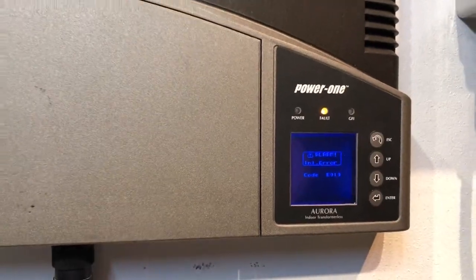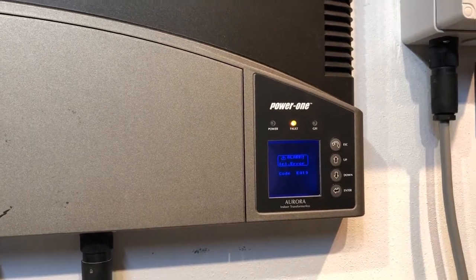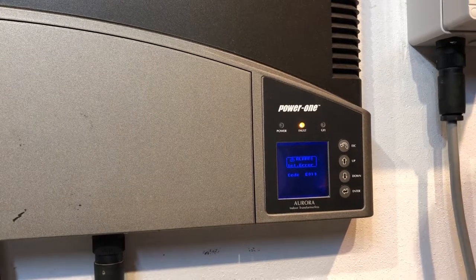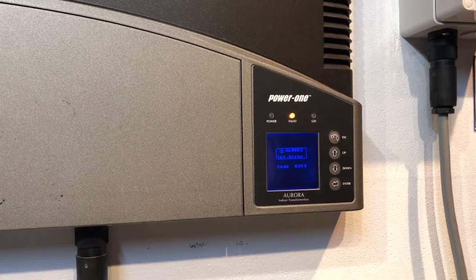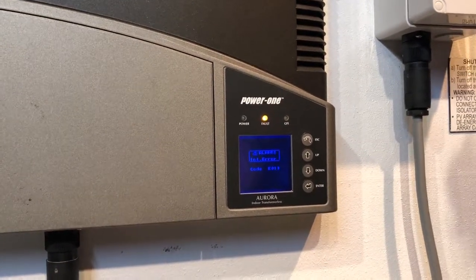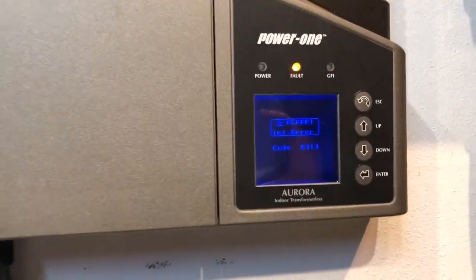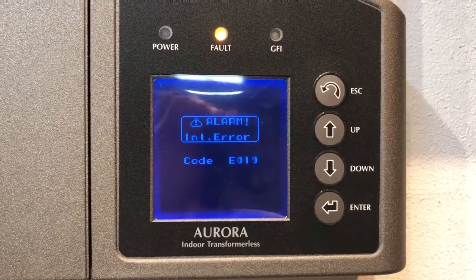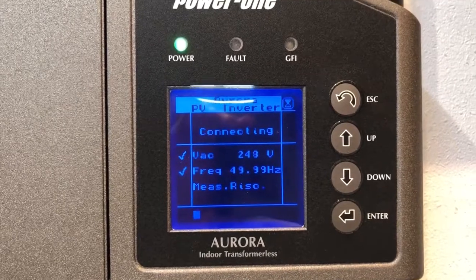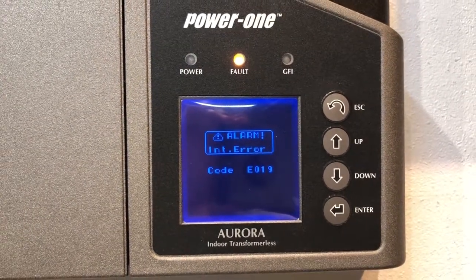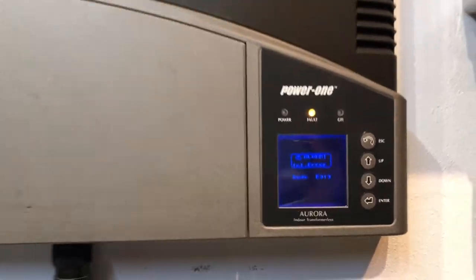You can see the orange fault lights on there now. The internal error code E019 on the Power One Aurora inverters is an internal error with the inverter. On startup, the inverter tries to do a test to make sure there's no earth leakage on the DC side — the solar panel side of the system. It does this internal test to verify it's reading the right information, and in this case that test has failed, giving us error code E019.